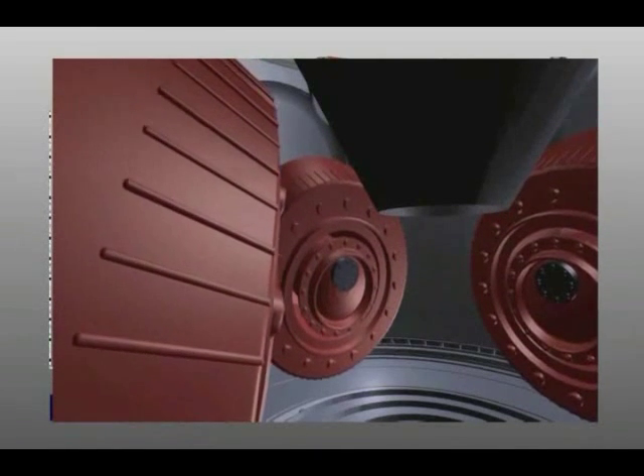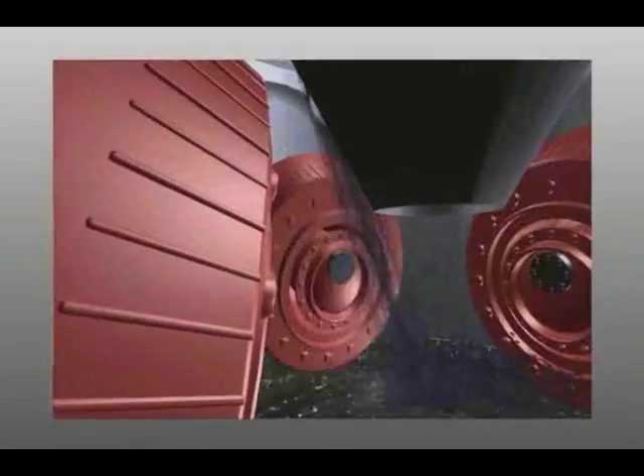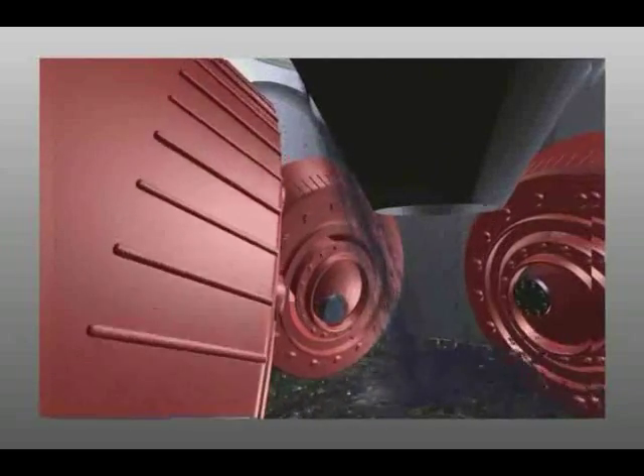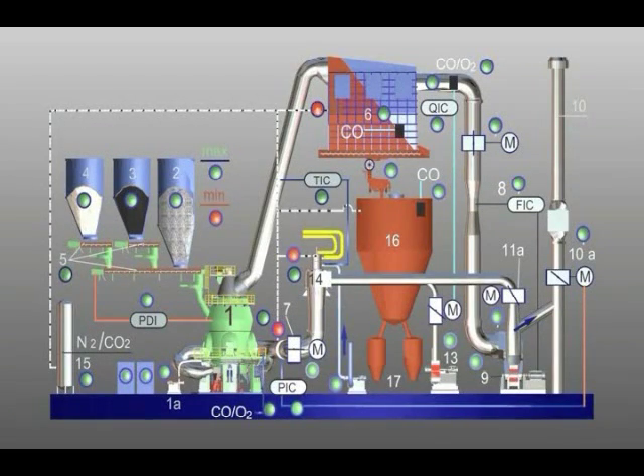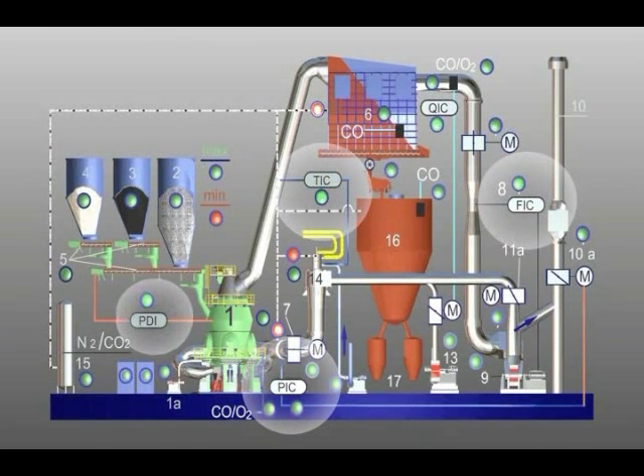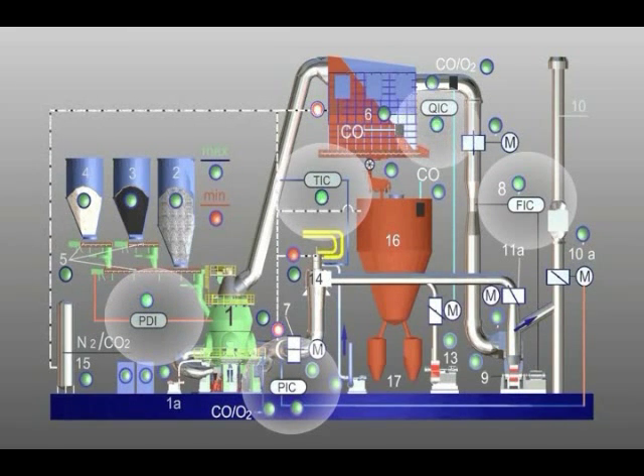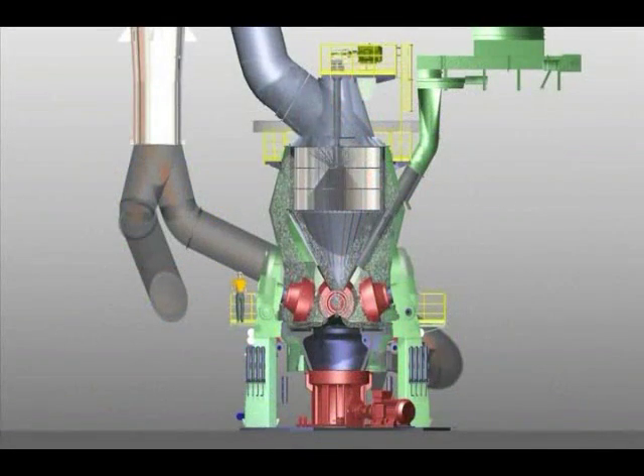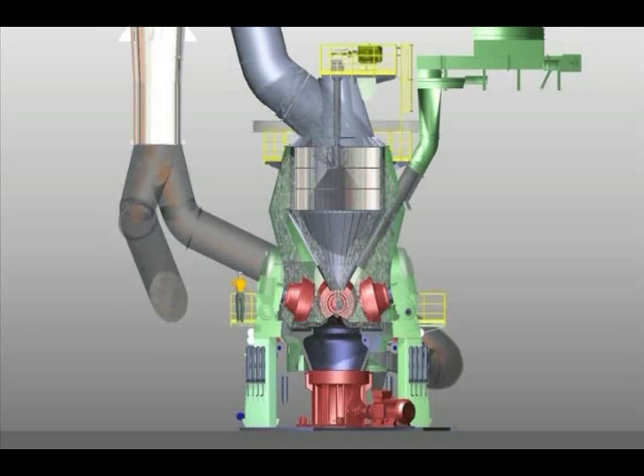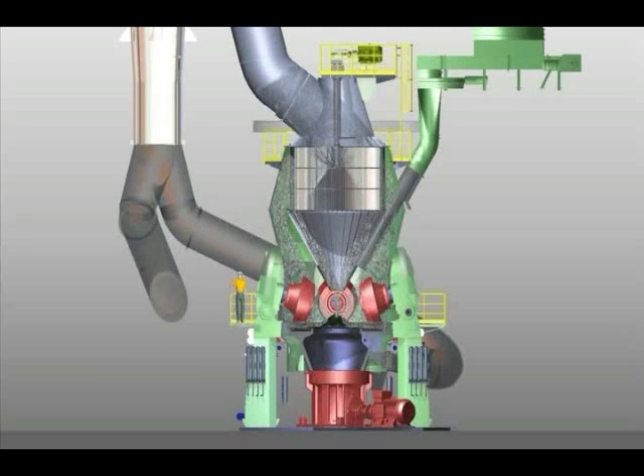Working pressure control is active, and the grinding rollers can be lowered. The material feed is set to the minimum throughput rate of 40%. All controllers and the associated controlled systems are set to automatic. TIC after mill, PIC before mill, FIC after filter, PDI mill differential pressure, QIC oxygen control after filter. The grinding plant is now performing self-inert grinding operation. Inert gases are no longer fed into the plant. For safety reasons, inert gas is only applied to the fine coal silo for the whole time that the grinding plant is running.